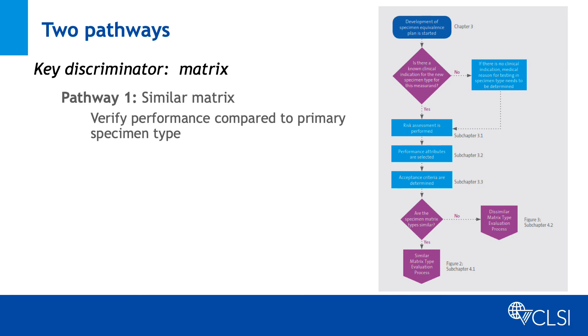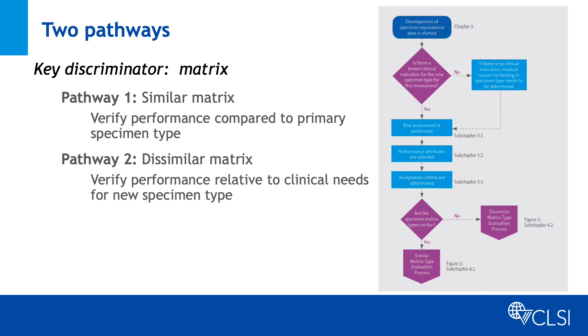For new specimen types with similar matrix, the studies are similar to those used to verify performance for a new implementation of an established measurement procedure. For new specimen types with dissimilar matrix, the studies focus on verifying performance is consistent with appropriate clinically based performance goals specific to the new specimen type.